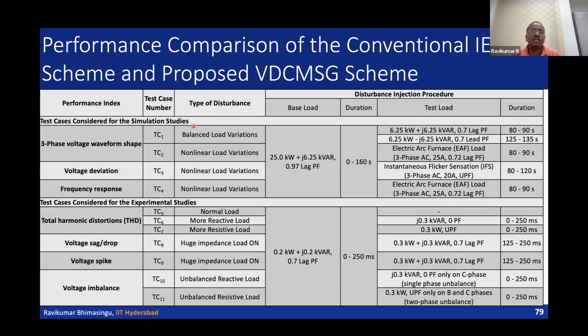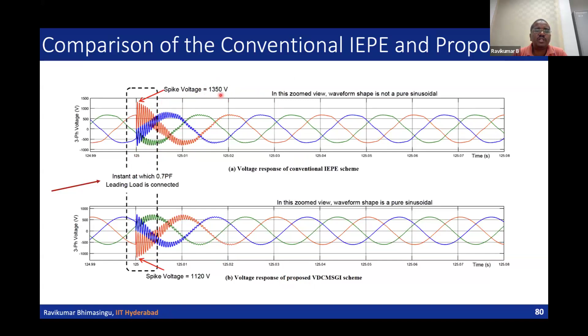This is the comparison of the conventional IEPE and proposed method. The top one is the IEPE based scheme's voltage response, and this is the proposed scheme's voltage response. You can see that the moment the leading load is connected, the spike voltage goes up to 1350 in the conventional scheme, whereas here it is 1120.